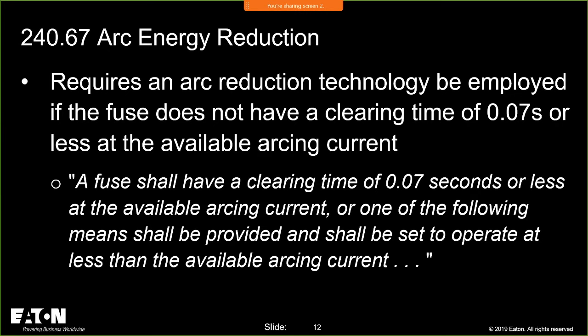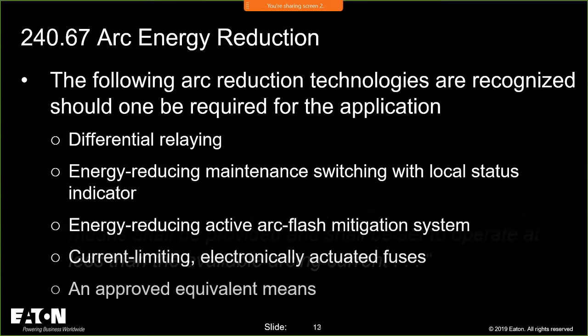So what's going to happen is you're going to have to, A, calculate the bolted fault current, B, calculate the arcing current, the minimum arcing current, and then take a look at the trip curves to see if it applies. And that's why the Bussmann tool is really critically important.